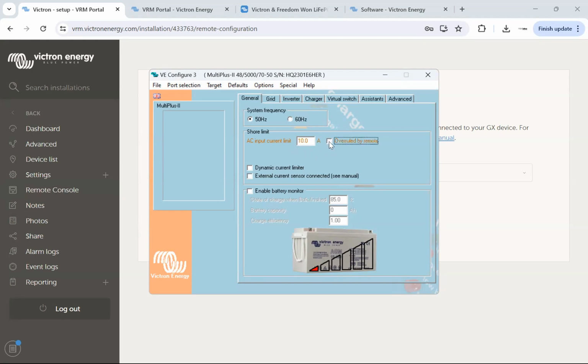Now, overruled by remote basically means you can get into the GX device and overrule that 10 amp limit if you want to. This is really good for generators that might struggle at 10 amps but be fine at 9 or 8, or if you want to vary it to get the maximum out of the generator, or treat it nicely. I normally do tick overruled by remote—it means you don't have to download the file, change it, upload it again, and then test it. You can test it on the fly through the screen or through the remote console.